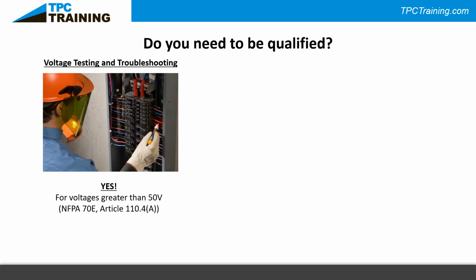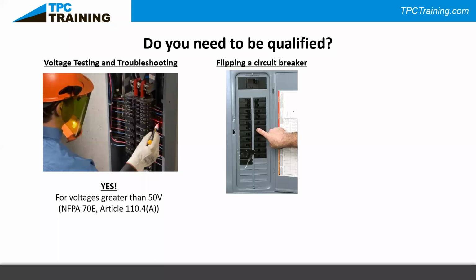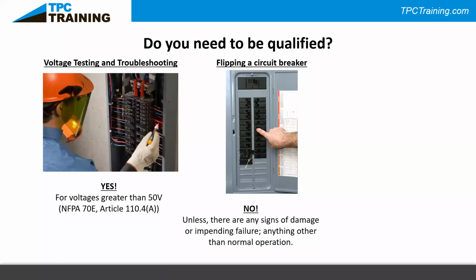Let's talk about this second task: flipping a circuit breaker. This is a common one we get. Do you need to be qualified to flip a circuit breaker on and off? The answer is no, you don't need to be qualified under normal circumstances. But here's my big caveat: if there are any signs of damage, impending failure, or strange operation—anything other than perfectly normal operation—then you do need to be qualified.